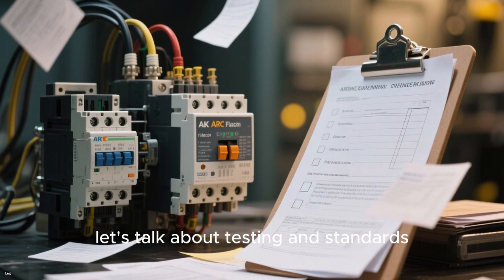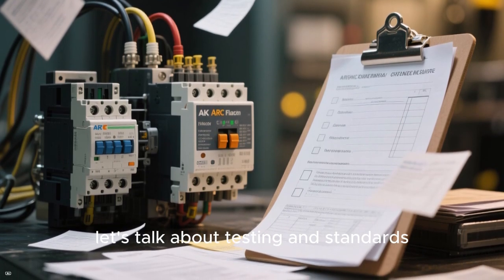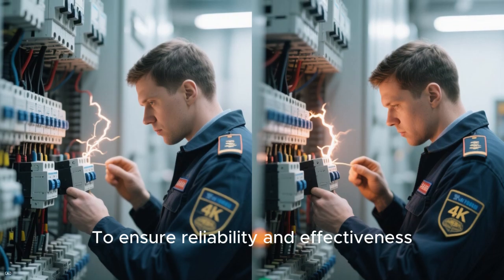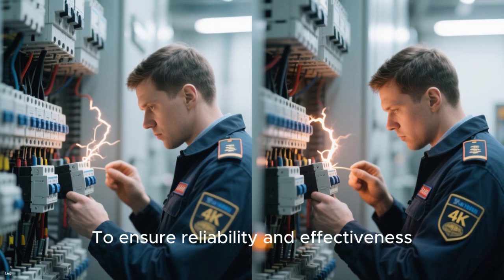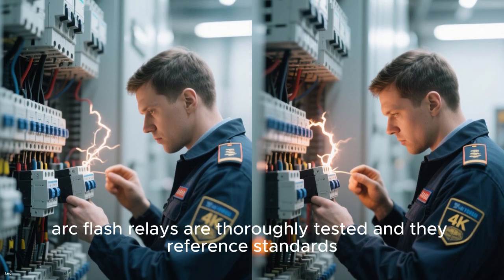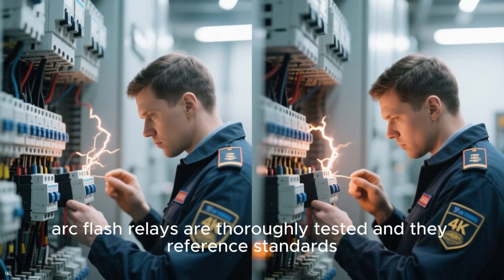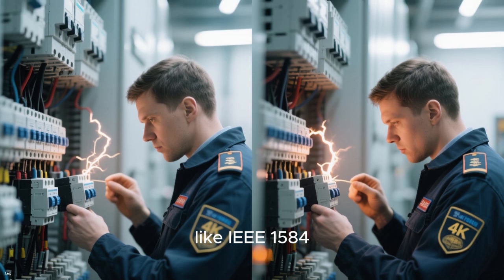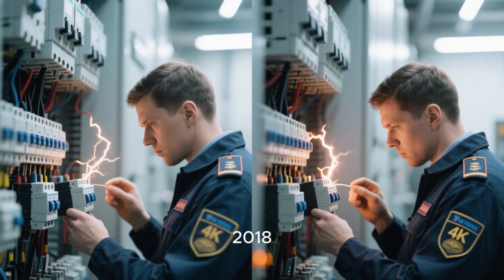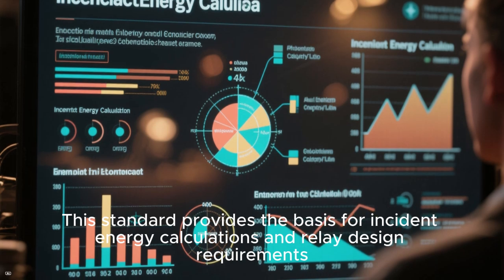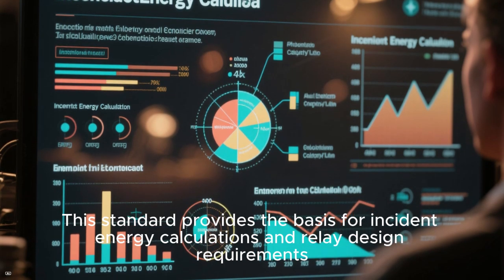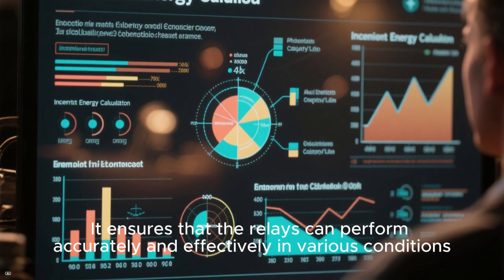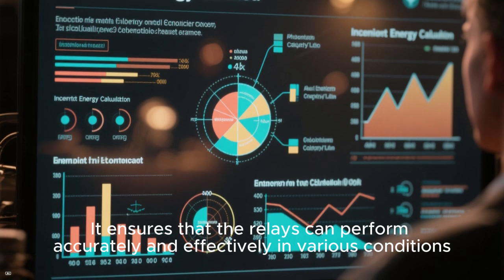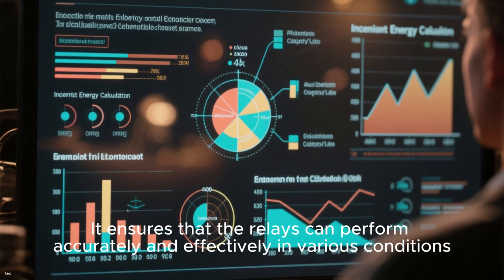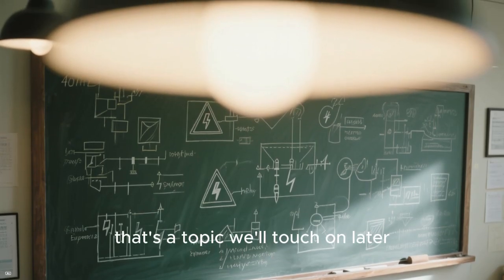And finally, let's talk about testing and standards to ensure reliability and effectiveness. Arc flash relays are thoroughly tested, and they reference standards like IEEE 1584-2018. This standard provides the basis for incident energy calculations and relay design requirements. It ensures that the relays can perform accurately and effectively in various conditions. And again, that's a topic we'll touch on later.